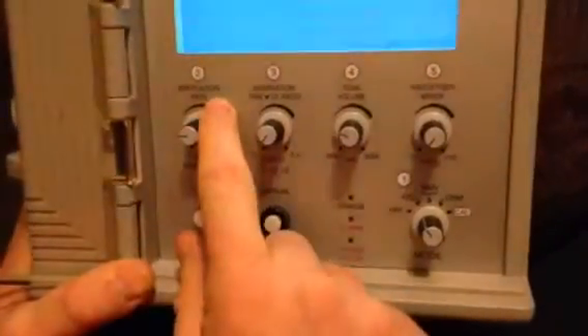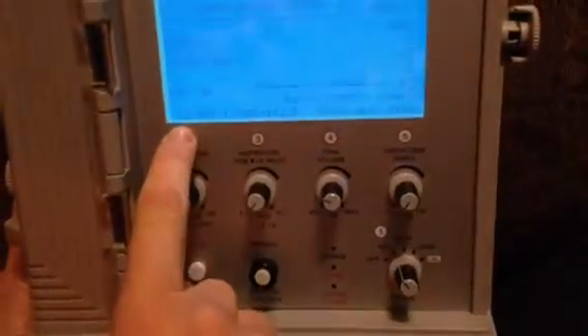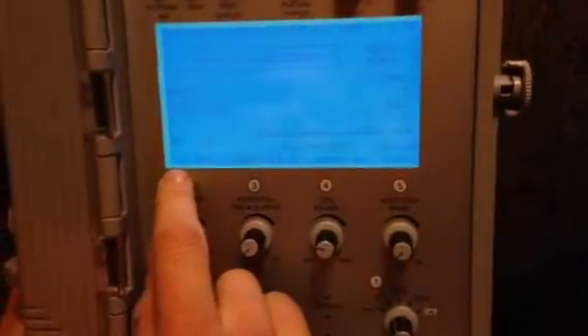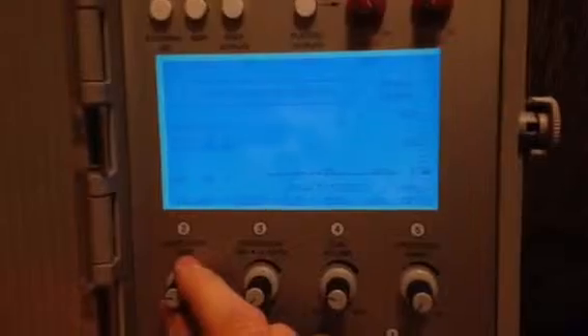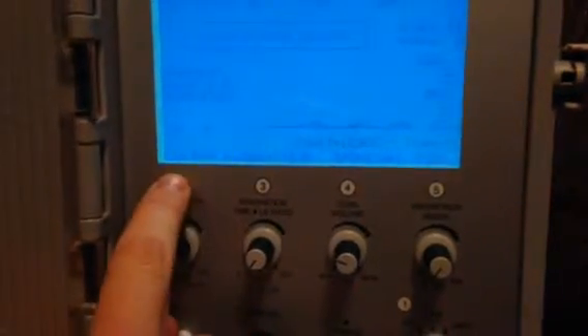All right, let's move on to step 2, which is the ventilation rate, or how many breaths per minute the ventilator is going to deliver. If you can see right now, it's set for 12 breaths a minute. If you can zoom in on that. All right, cool. Just to show you how the knobs work, we're going to set it for 16 breaths a minute. They're very sensitive, so you use just small touches. So now we're set at 16 breaths a minute.